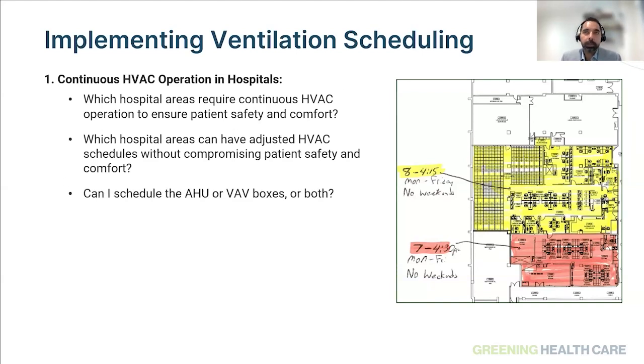Then there are questions that usually come in because our facility is an older facility. We don't have building automation systems to a point that we can schedule VAV boxes, or we currently don't have airflow controls. How can we schedule some of these systems? We'll talk about this with Jared from Medicine Hat today. They had a similar situation in their facility, where half of the facility was DDC controlled with VAV boxes and CAV boxes in many of the departments, and the other half is traditional constant volume ductwork with a supply and return and no zone level control. But they were able to do the scheduling, and we'll have more of that. So it is practical to do these measures with or without controls.